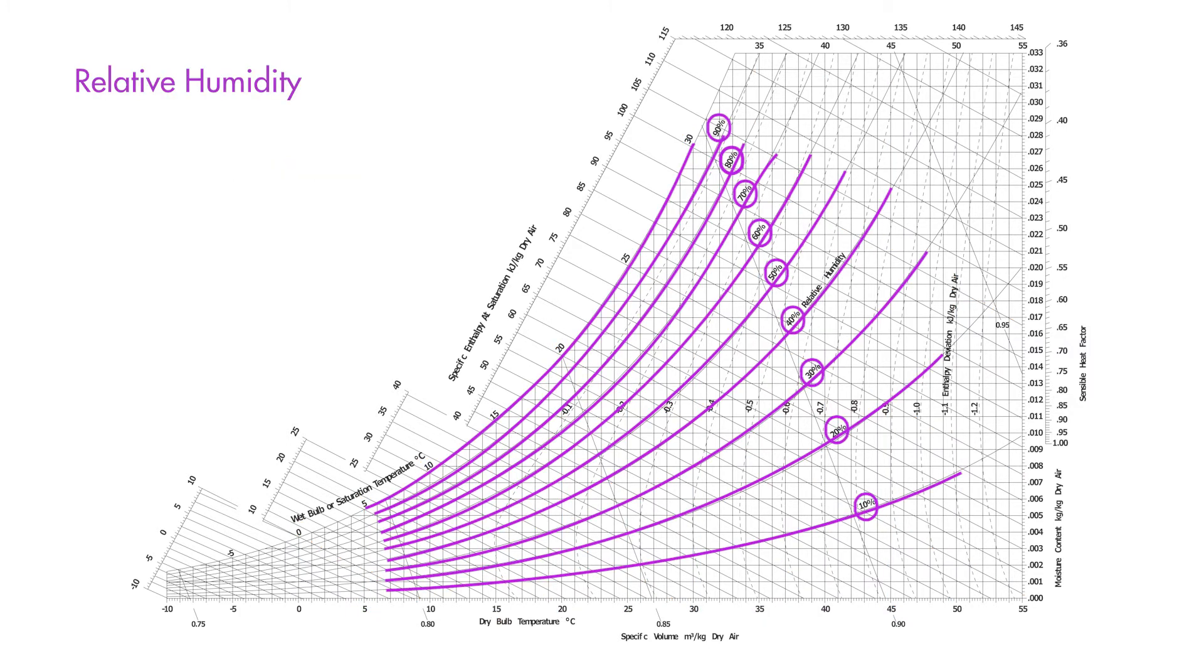The purple lines represent relative humidity. Relative humidity is the percentage of moisture the air is holding relative to the maximum amount it could hold at a given dry bulb temperature. So for example, 50% relative humidity means that the air is currently holding half the moisture it could potentially hold at the current temperature.